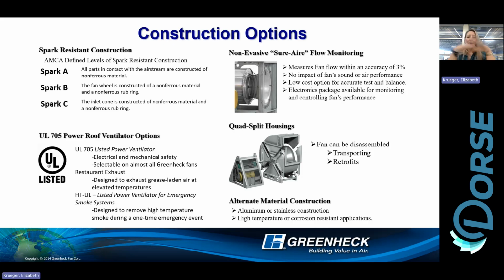Now, I know that Blake had hit on stairwell pressurization. The fans I've seen used for stairwell pressurization go along with that UL listing for smoke exhaust, for emergency smoke ventilation. Sometimes they do need that UL listing, sometimes not. But the USF is a perfect fan for that, because it has the option to build a lot of pressure. They are meant to be outdoors, and you can change the configuration of the discharge, so if you need to discharge in a certain direction, you can.